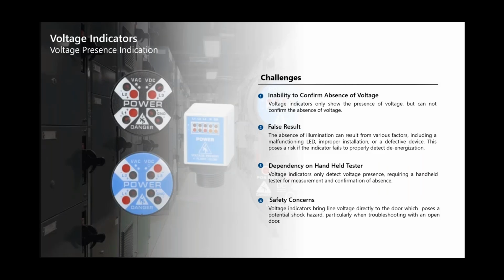So the main challenge with a voltage indicator is its inability to confirm absence of voltage. Voltage indicators only show the presence of voltage, but cannot confirm the absence of voltage. There could be false results. The absence of illumination can result from various factors, including a malfunctioning LED, improper installation, or a defective device. This poses a risk if the indicator fails to properly detect de-energization, and that's why it cannot be used for absence of voltage testing. There's also a dependency on a handheld tester, where a voltage indicator only detects voltage presence, requiring a handheld tester for measurement and confirmation of absence through the ports.